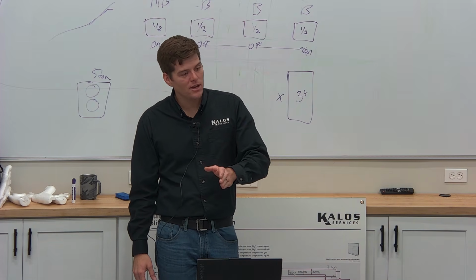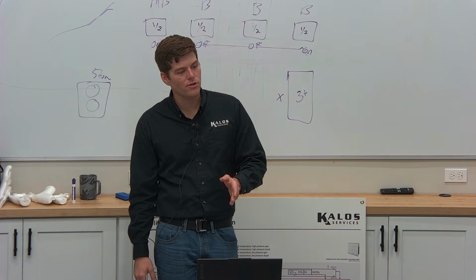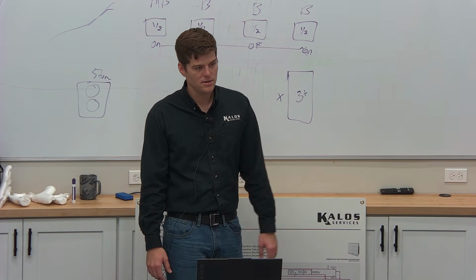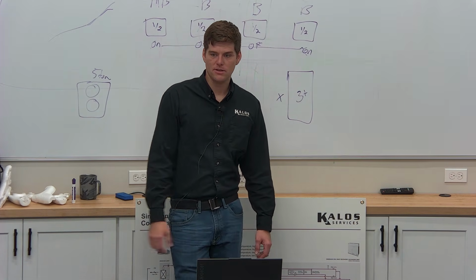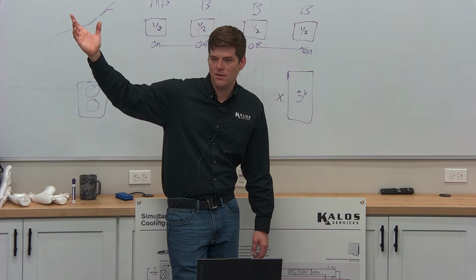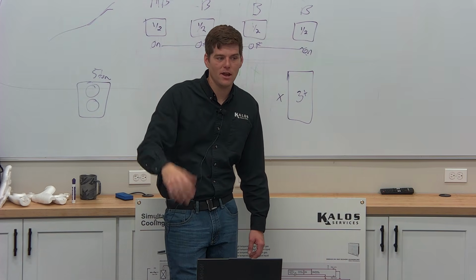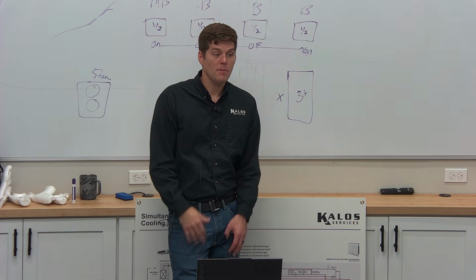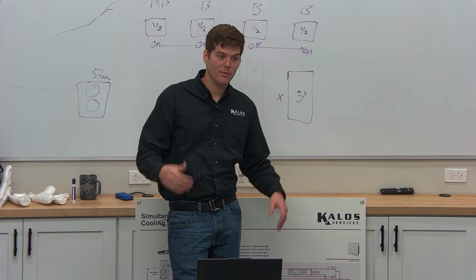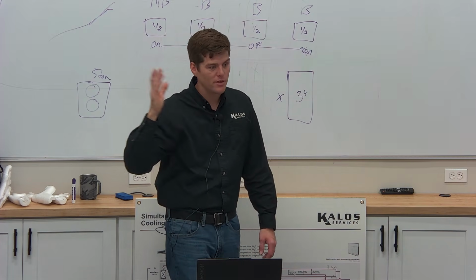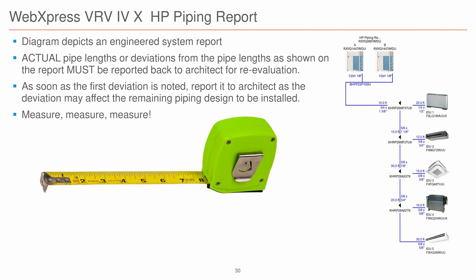But if I never calculated that and never wrote it down in installation, I would have never known that that liquid line is undersized. And I ran it in 3/8 anyways, because that's what the program says, right? The program doesn't know that it's actually 350 feet, not 50 feet. My unit is never going to perform correctly. It's never going to deliver the capacity it needs to that fan coil. That's why this is so important. This is where 98% of contractors miss the mark.